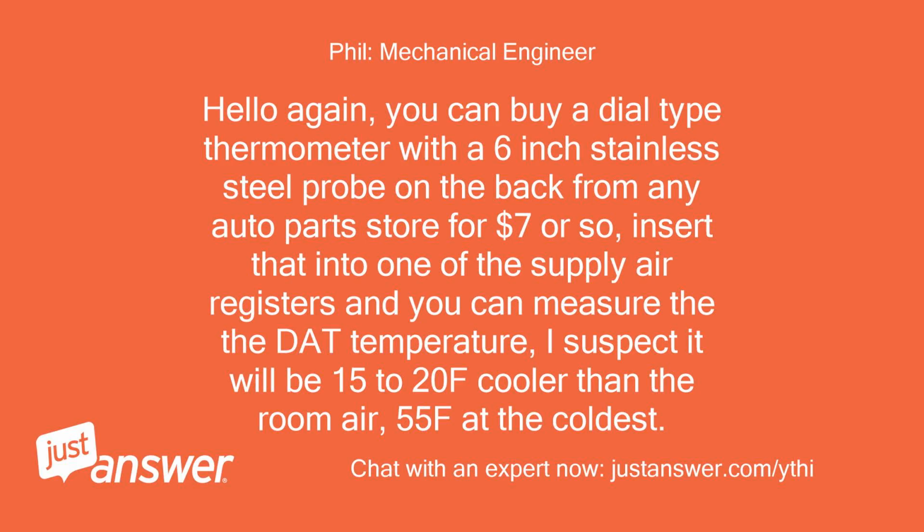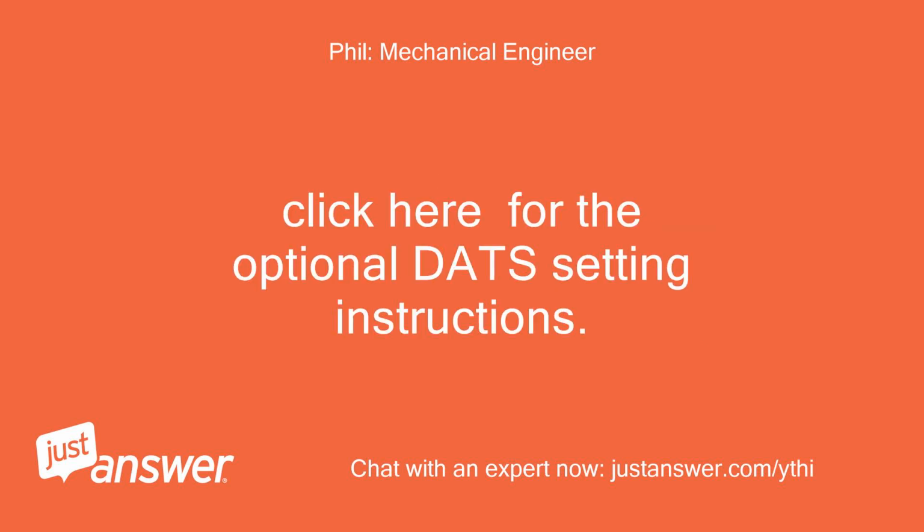Hello again. You can buy a dial-type thermometer with a 6-inch stainless steel probe on the back from any auto parts store for $7 or so. Insert that into one of the supply air registers, and you can measure the DAT temperature. I suspect it will be 15 to 20 F cooler than the room air, 55 F at the coldest. Click here for the optional DATS setting instructions.